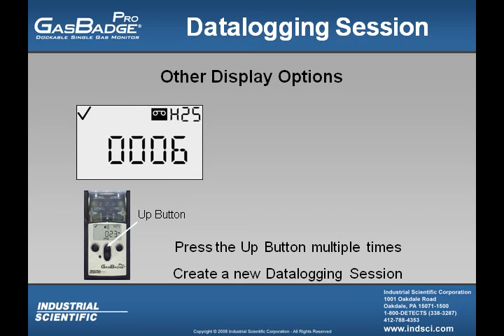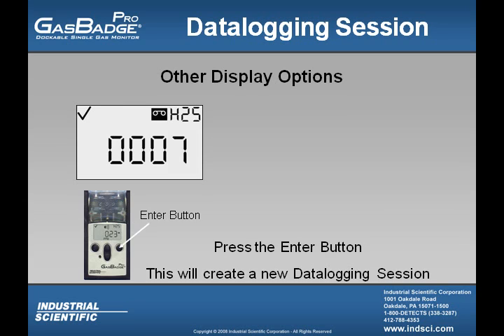The GasBadge Pro also has a data logging option. The instrument will continue to record the gas readings the instrument sees within a specified amount of time. The user can create a new data logging session by pressing the Up button multiple times until they see the tape icon appear just like the one shown. If the user wants to create a new data logging session, they can press the Enter button and the numerical value will step up 1 and a new data logging session is started.